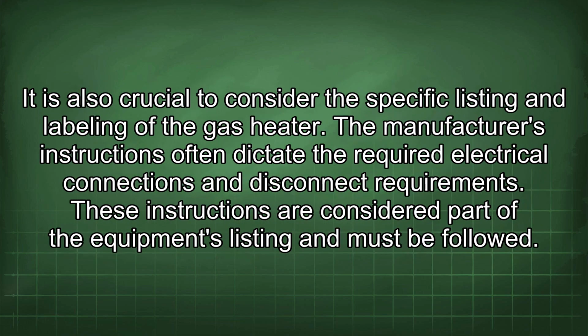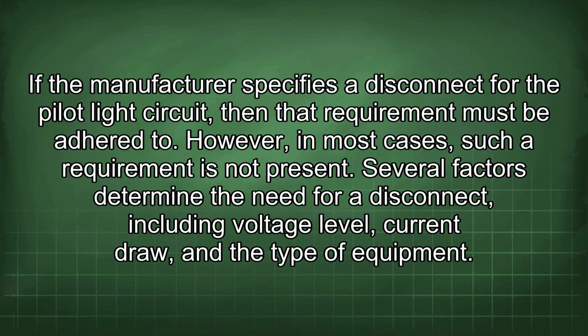It is also crucial to consider the specific listing and labeling of the gas heater. The manufacturer's instructions often dictate the required electrical connections and disconnect requirements. These instructions are considered part of the equipment's listing and must be followed. If the manufacturer specifies a disconnect for the pilot light circuit, then that requirement must be adhered to. However, in most cases, such a requirement is not present.